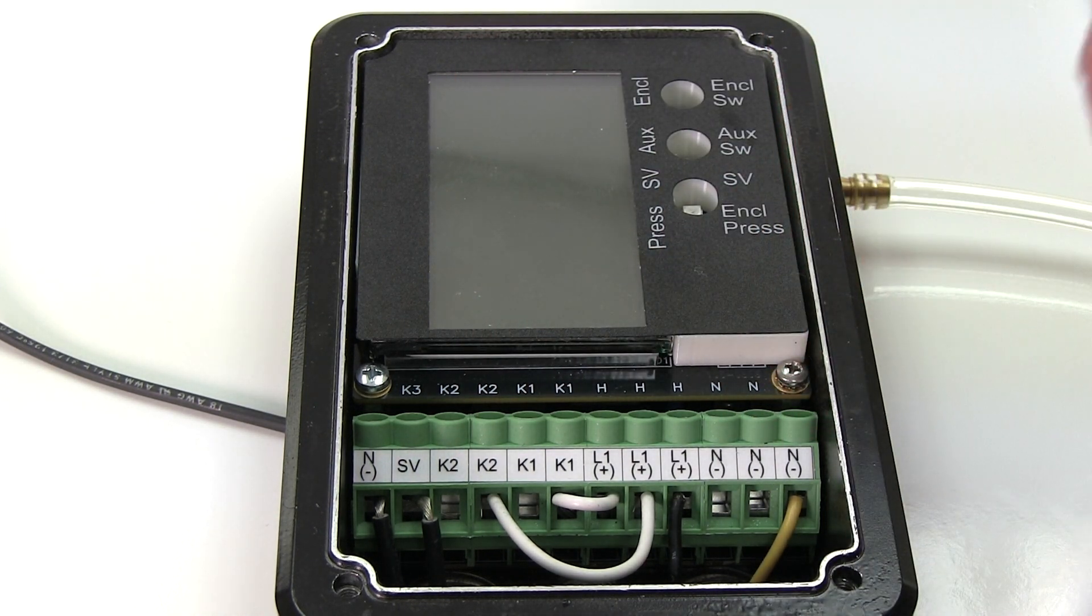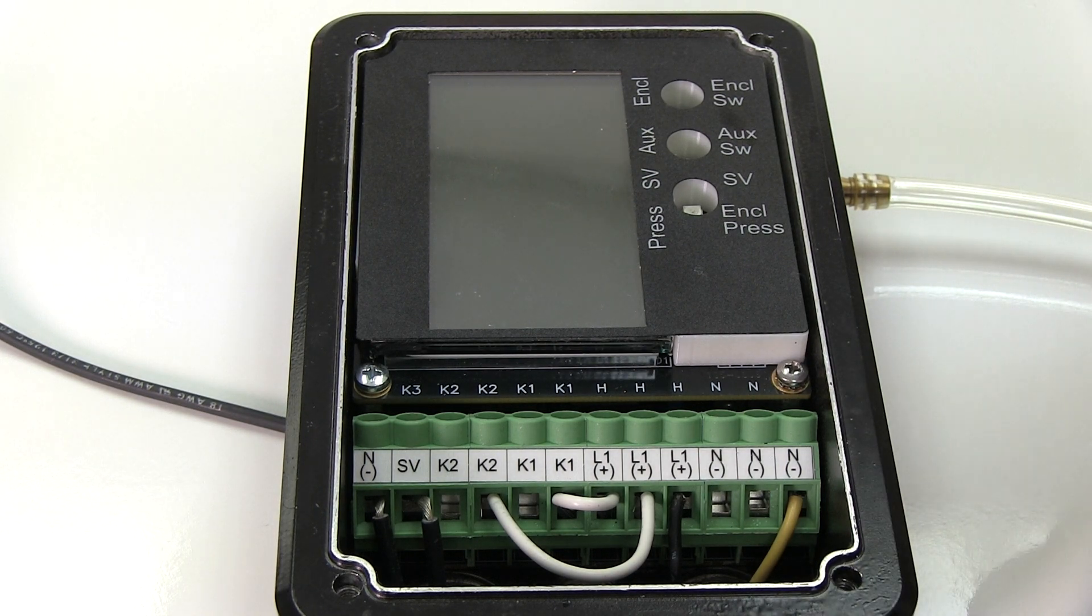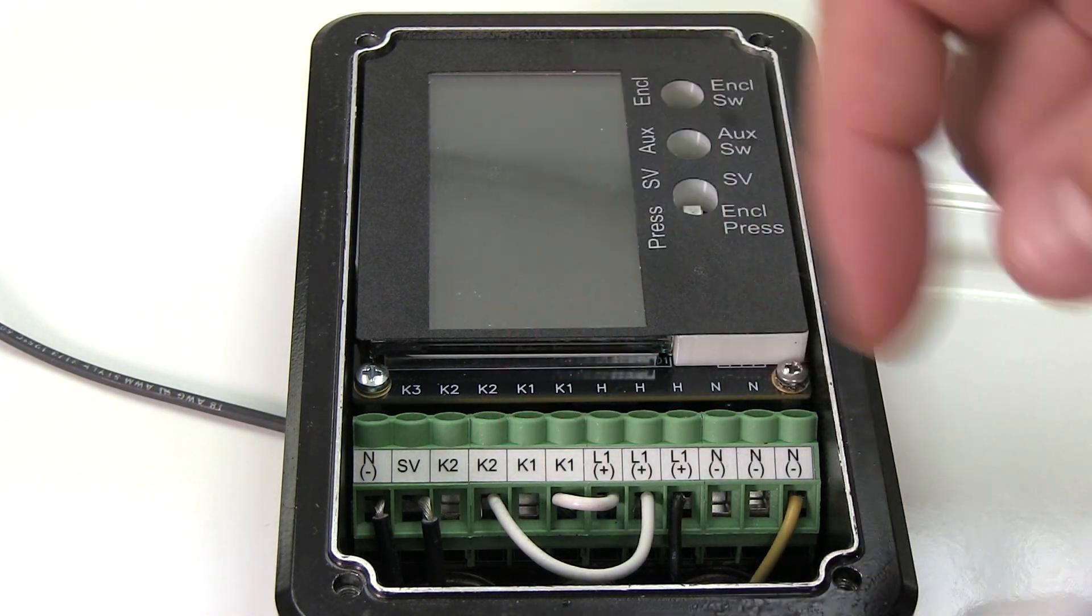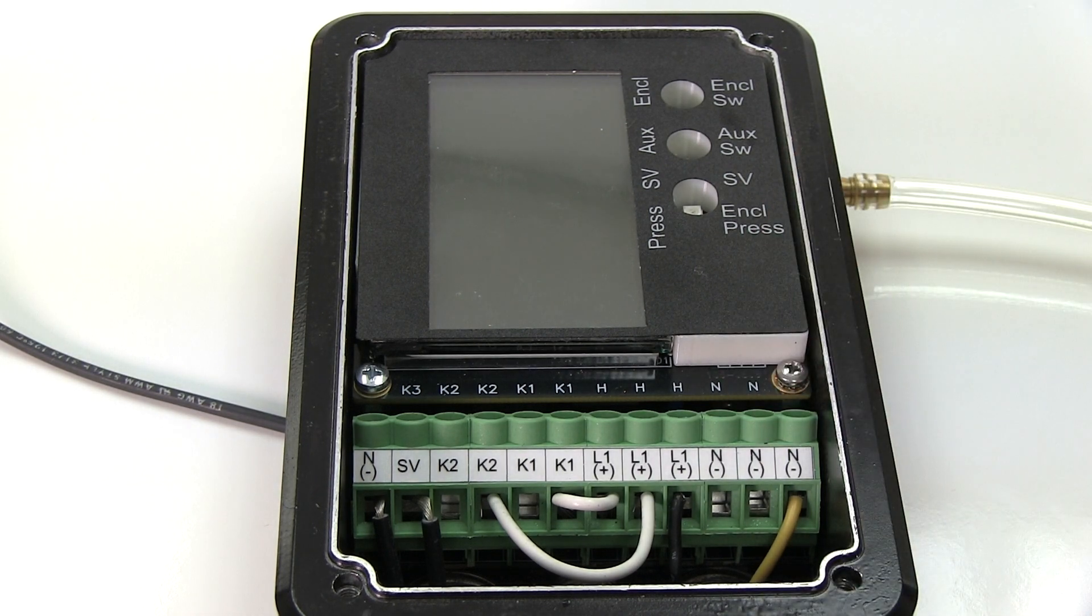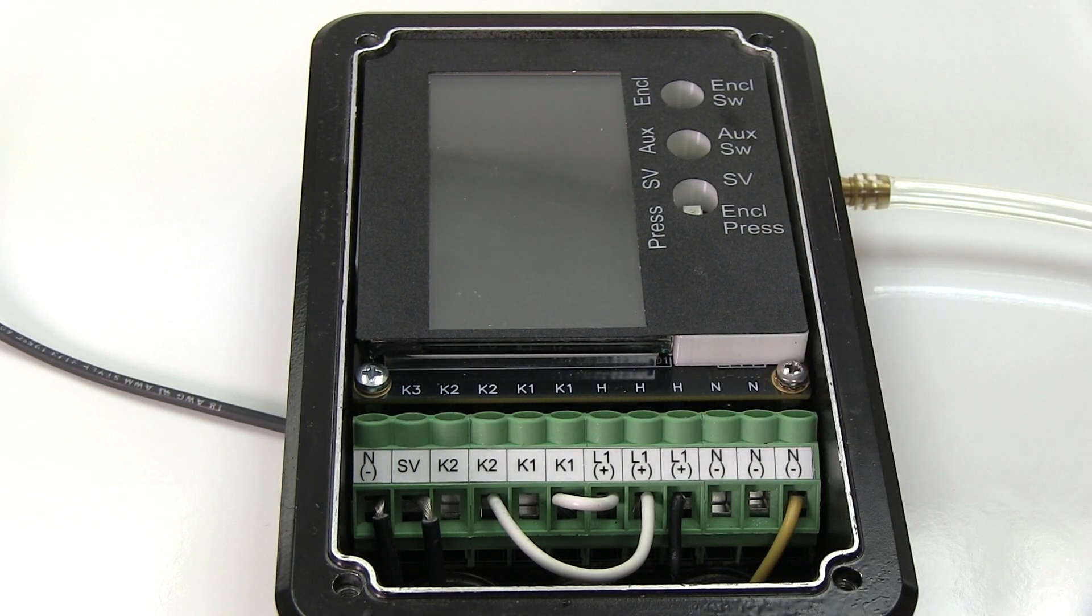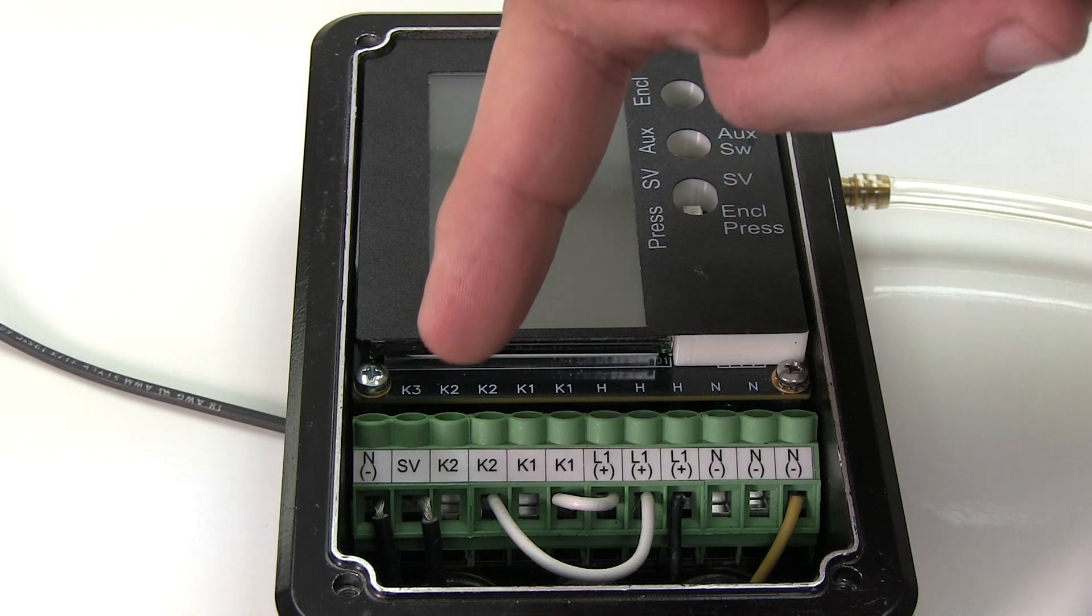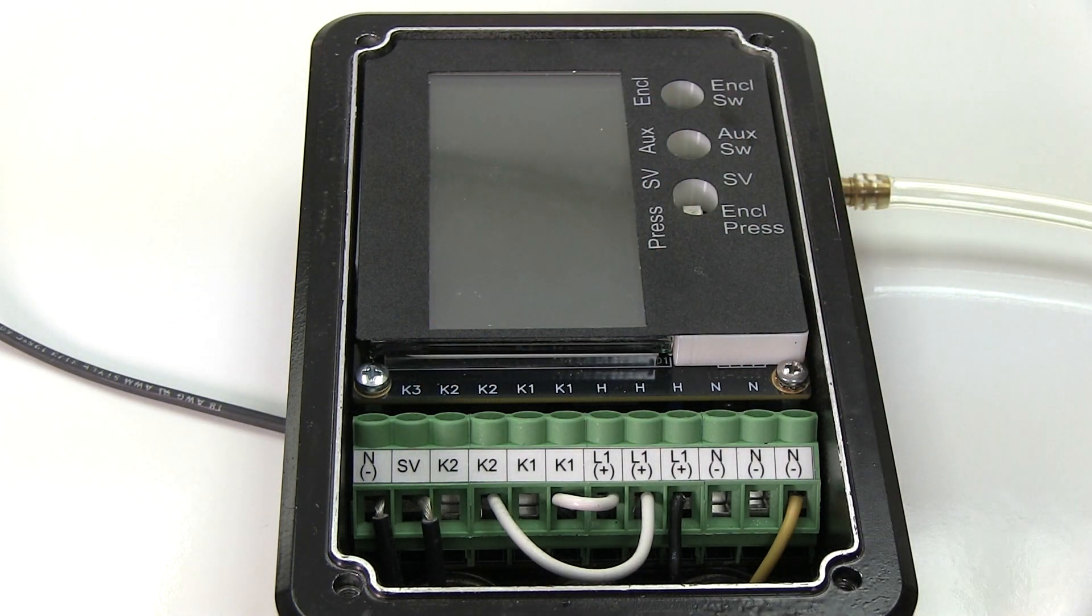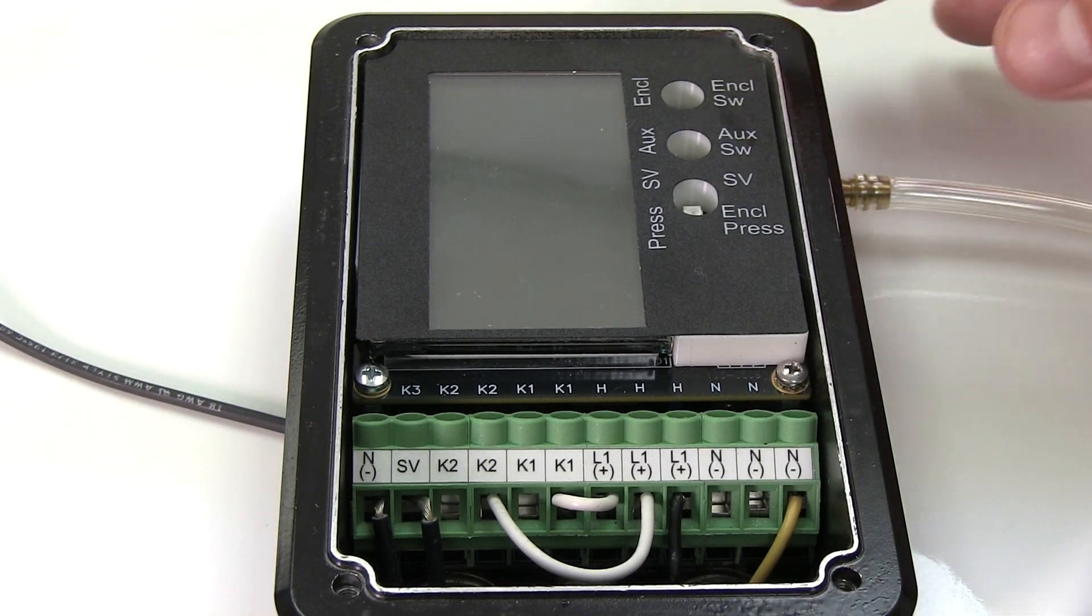So as of now, all I would have to do would be to wire up my enclosure. I would just take a wire from K1 to my enclosure and then wire it back up to one of my neutral terminal blocks. Same thing with my alarm contact. I would just take the K2 contact to my alarm and then bring it back and connect it to the neutral.